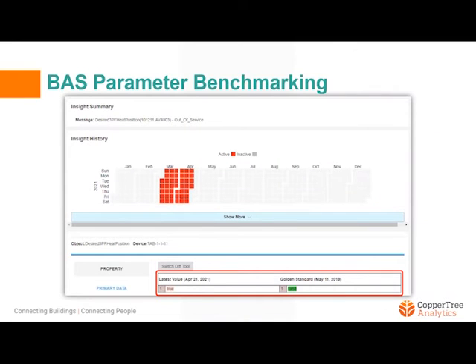BAS Parameter Benchmarking. When you have a building that is considered fully commissioned, really what you're saying is everything is working as it should be, and you hand over the building to the building owner, the building occupants, or I should say the building facilities operators who take care of the occupants in the building. Now, what a feature like this, which is our golden standard feature, does is it always compares your new data with the golden standard, which is from a perfectly commissioned state, meaning new data each day from the building is compared with the golden standard, the perfect commissioned state of the building.